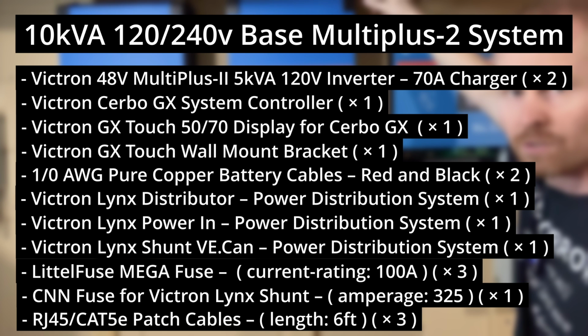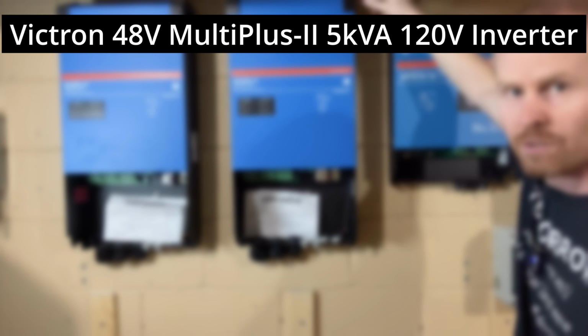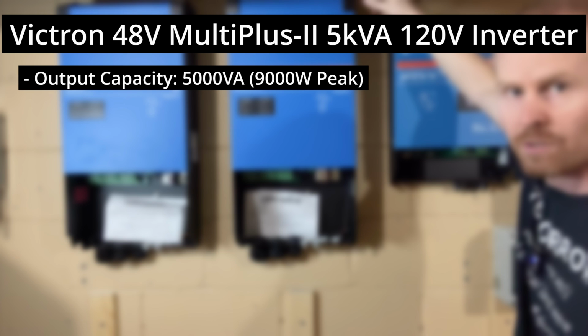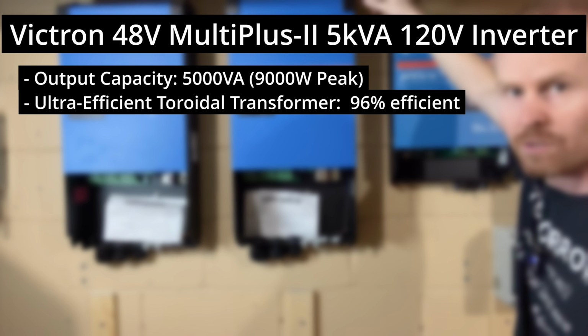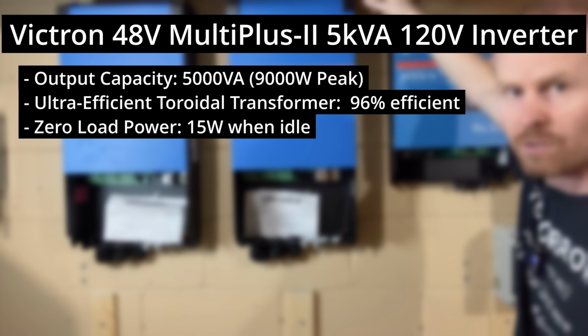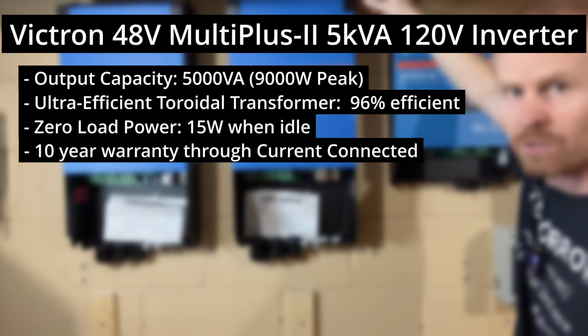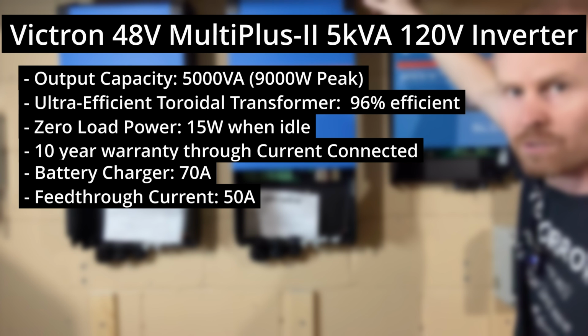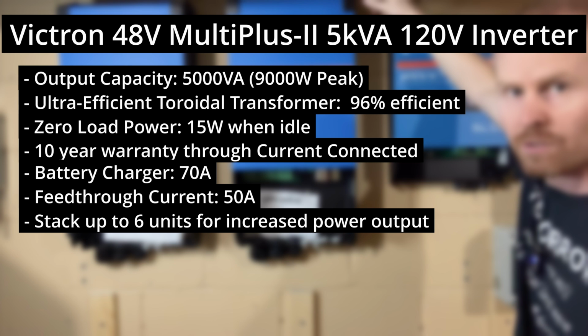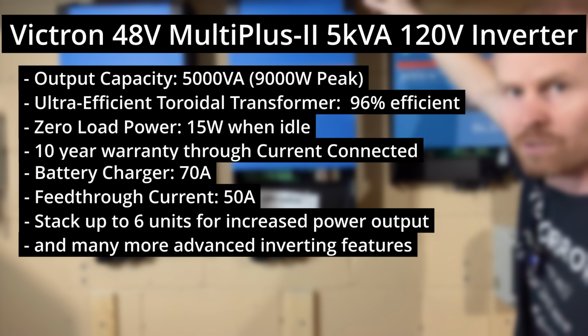It is pre-configured by Current Connected for 120/240 split phase, and you can always add additional inverters and stack more for additional output. Now the MultiPlus-II inverters themselves are 5 kVA apiece. They are built with a toroidal transformer which is 96% efficient, and they have an unprecedented 15 watt idle capacity. These inverters also come with a 5-year manufacturer warranty and a 5-year Current Connected extended warranty, which gives you a total of 10 years of warranty on your inverters, which is amazing. It also has a 70 amp battery charger with a 50 amp feed-through current. You can stack up to 6 units for increased power output. And it also has a whole lot more advanced inverting features that you might not see in other inverters.